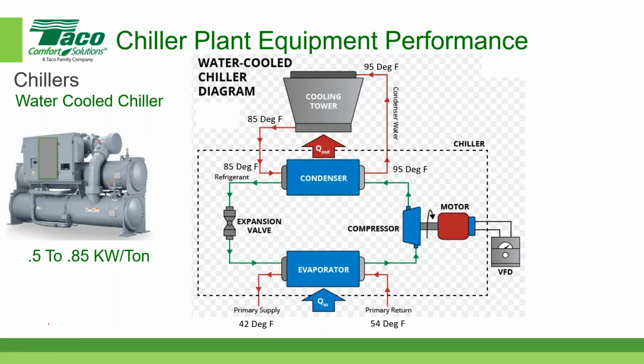Okay, so let's add some more temperatures in there. So now we're seeing that the refrigerant temperature is 32 degrees in our simple example here. It may not be in the real world. Refrigerant might be slightly different in temperature, but you get the general idea. The refrigerant temperature has to be below the supply water temperature as it enters the evaporator, and then the refrigerant temperature has to be above the condenser water temperature here.